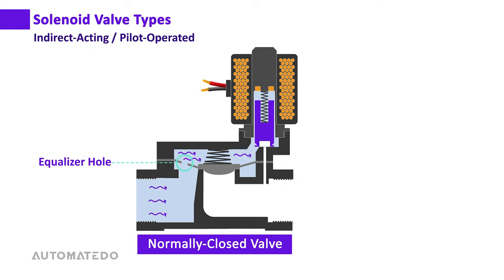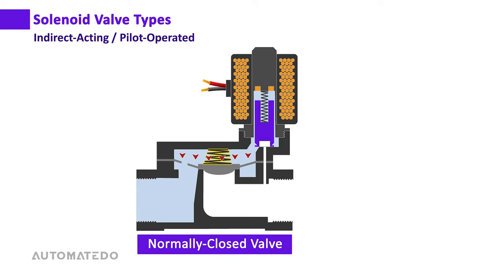Media flows from the inlet through the pinhole into the upper chamber, equalizing pressure in both chambers. However, the pressurized media in the upper chamber acts across a much broader area of the diaphragm than the media at the inlet. Therefore, the downward force above the diaphragm is greater than the upward force below it, keeping the valve closed.